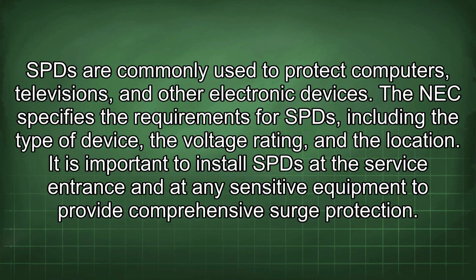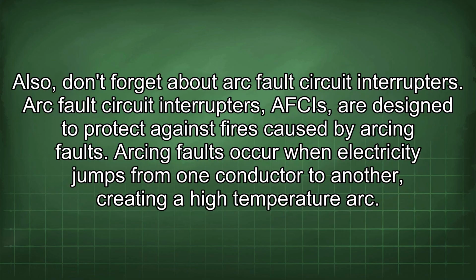SPDs are commonly used to protect computers, televisions, and other electronic devices. The NEC specifies the requirements for SPDs, including the type of device, the voltage rating, and the location. It is important to install SPDs at the service entrance and at any sensitive equipment to provide comprehensive surge protection. Also, don't forget about arc fault circuit interrupters.